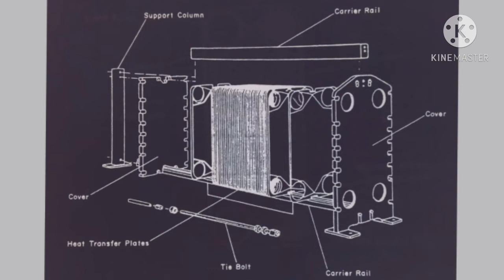Another important point is leaking plates can be removed in pairs if necessary, without replacement. Maintenance is simple. Turbulent flow helps to reduce deposit buildup which would interfere with heat transfer. Because of the existence of turbulent flow, deposits are reduced, which helps maintain heat transfer efficiency.